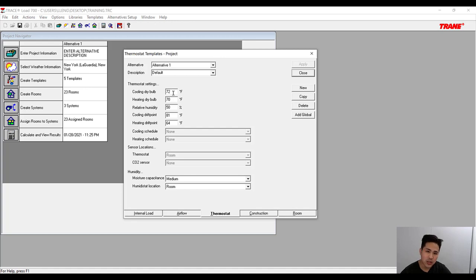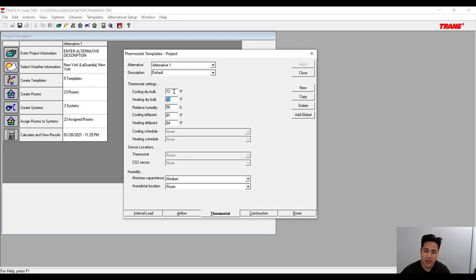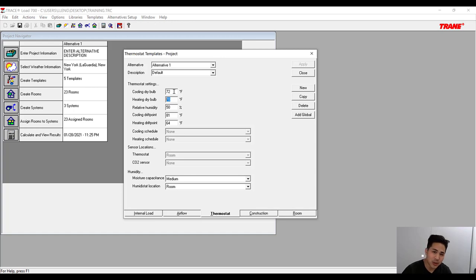In the thermostat tab, we're going to set the cooling setpoint temperature to 72 degrees, which is the standard setting for cooling. For heating it will be a little bit less — 70 degrees — because if heating is higher than cooling they oppose each other. You can't have heating at 72 and cooling at 70 since that would oppose the equipment. Relative humidity we'll keep at 50%, and we'll keep the cooling and heating dewpoints at their default numbers.